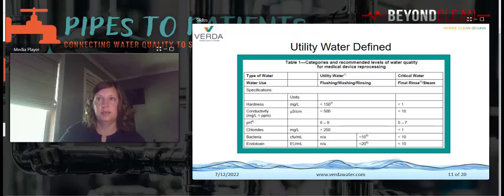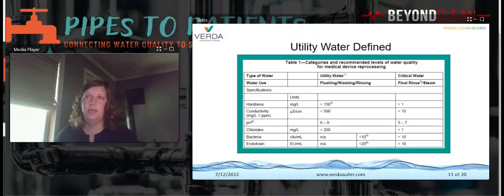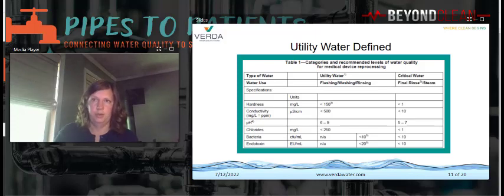Conductivity levels provide an overall sense of organic and inorganic matter in the water. If the conductivity is low, then chloride, chlorine, iron, copper, etc., are all expected to be low as well. Keeping the pH within specified ranges is important to maintaining optimal performance of the washer detergents and their cleaning capability. pH levels that are too high or low can also promote staining of instruments. Chlorides are the salts that result from chlorine gas combining with a metal. Table salt is sodium chloride, that's sodium metal and chlorine gas. So chlorides will corrode even stainless steel instruments, and that's why it's very closely monitored. For utility water, chlorides have to be less than 250, but for critical water, they need to be less than 1 milligram per liter.